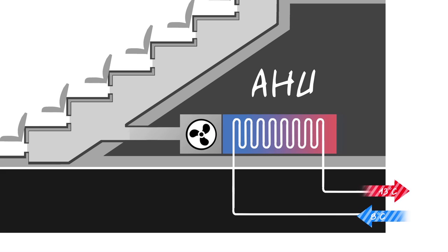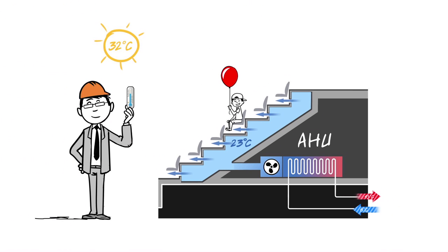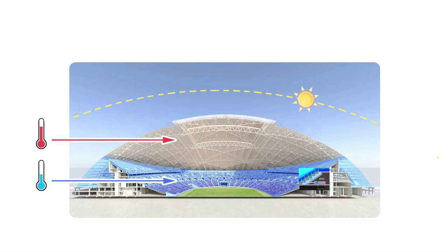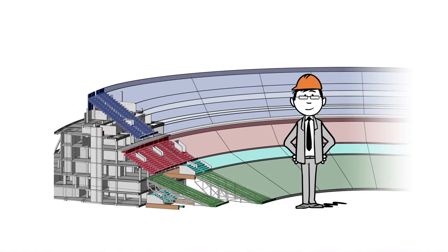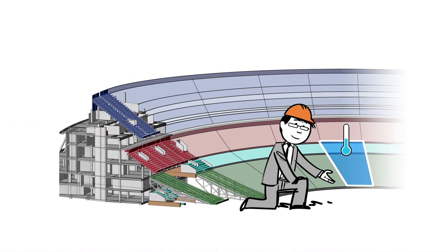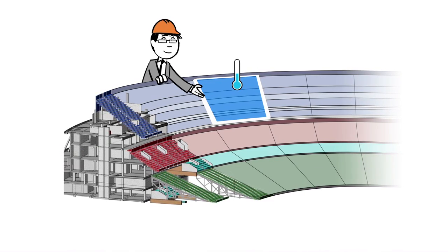Inside these units, the water cools the airflow, like a car radiator. So 23-degree freshened air gently flows through a slot beneath each one of the 55,000 seats. Only the atmosphere in the area we are sitting in is tempered by the bowl cooling, not the other empty bleachers. Each of the 116 air handling units can be activated separately in order to feed only the bleachers with spectators. So instead of air conditioning the entire bowl, we focus only on targeted stretches.